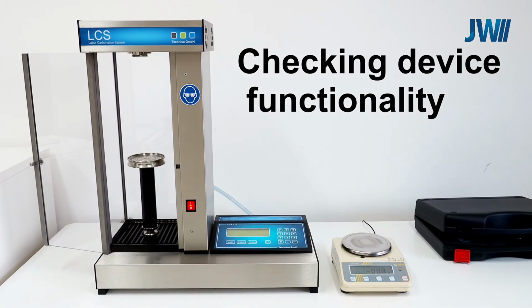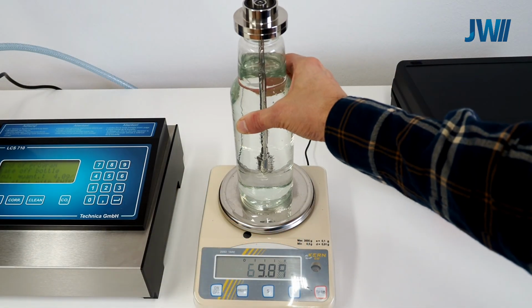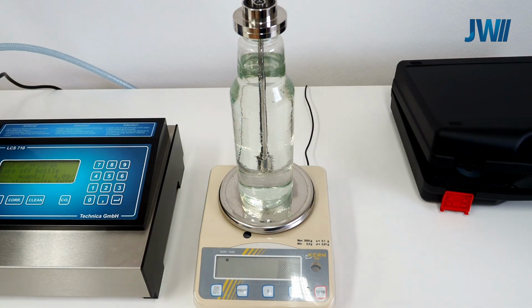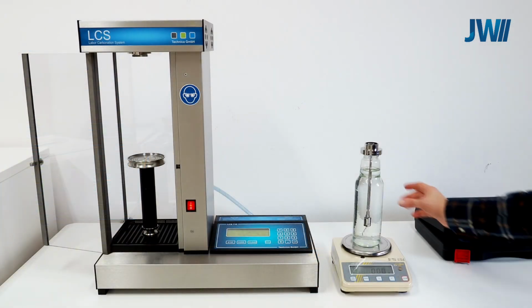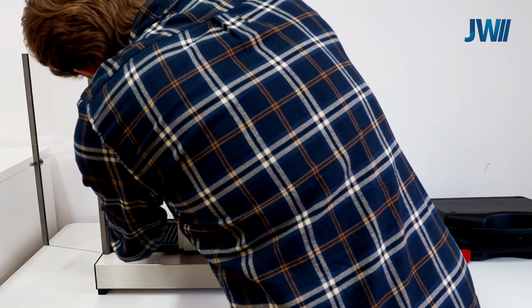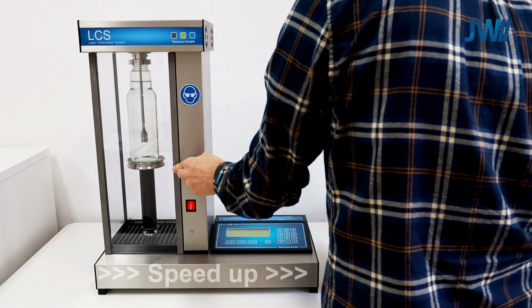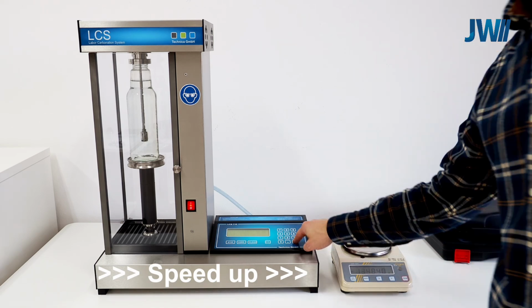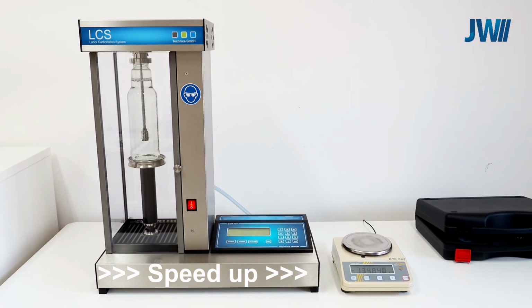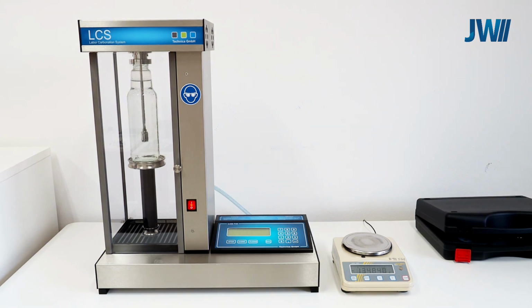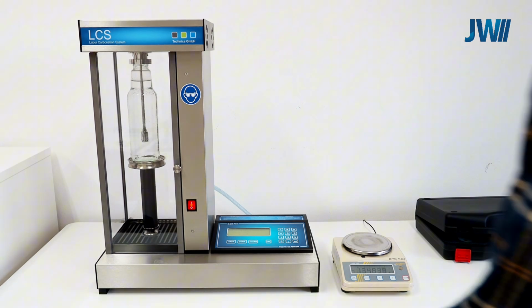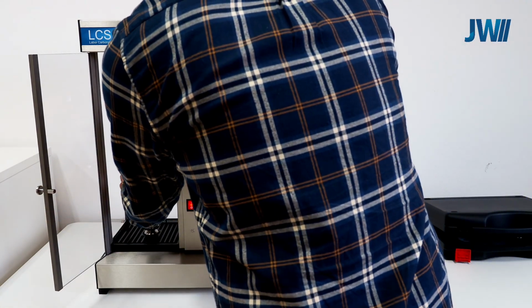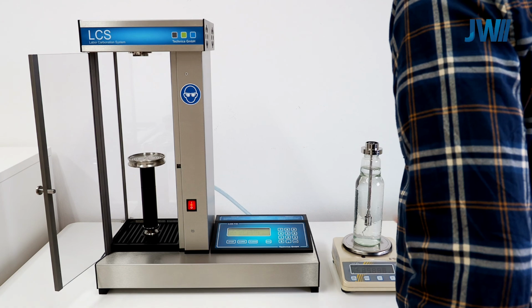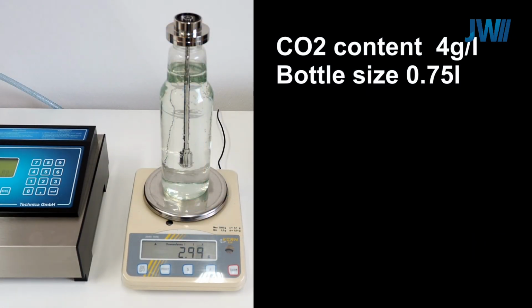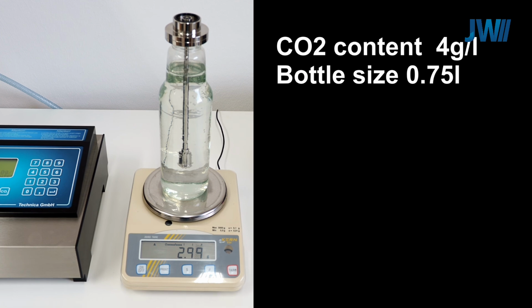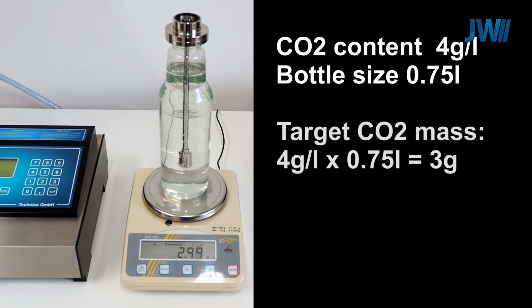The LCS also offers a simple way to check if the device is functioning properly. For this, you'll need a precision scale. Place a bottle with the probe head on the scale and zero it. Then, dose the bottle. You can measure the dosed weight on the scale. For example, I dosed 4 grams per L in a 0.75 liter bottle. We can calculate that I should measure 3 grams of CO2 mass.